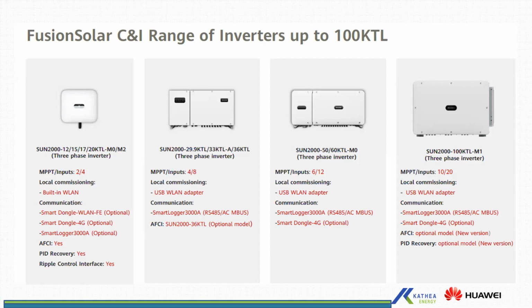We'll look at the schematic diagram of the inverters during our webinar. For the 12 to 20 KTL range, KTL is simply an abbreviation for kilo, which is 1,000, and the TL simply means transformerless inverter. So all the HUAWEI inverters are transformerless, and that's denoted by the TL. A 20 KTL inverter is equivalent to a 20 kilowatt inverter, which is the rated size. However, HUAWEI inverters can produce up to 10% more of their rating.